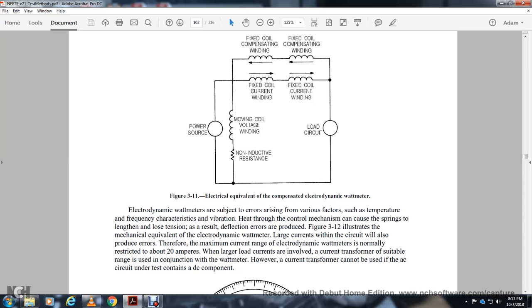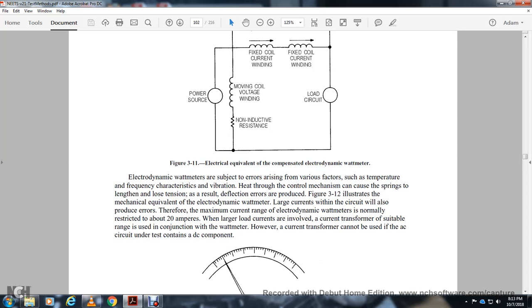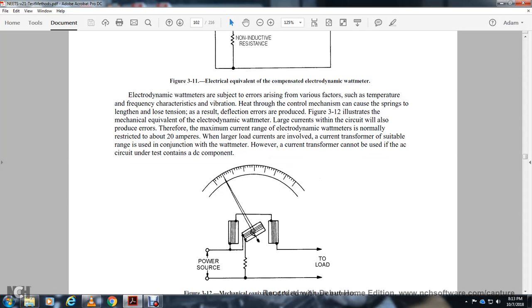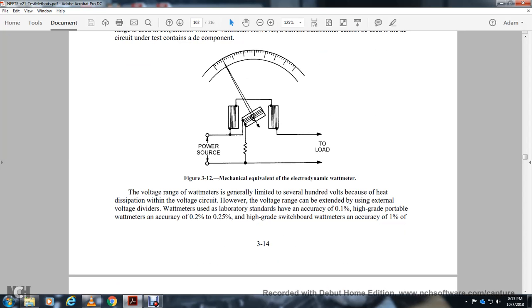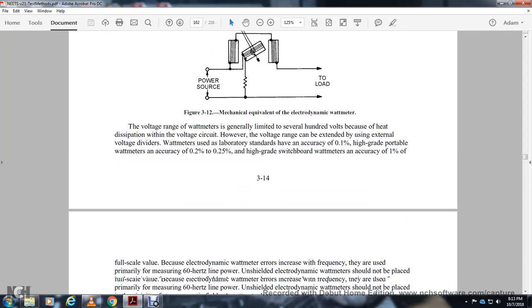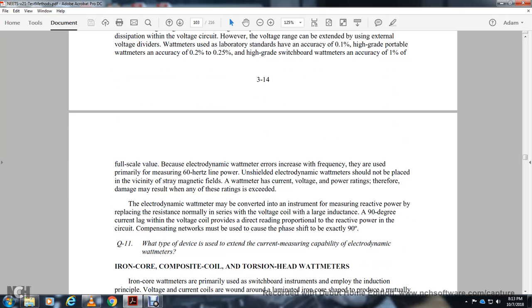The current transformer cannot be used if the AC current under test contains a DC component. The watt meter is generally limited to several hundred volts; external voltage dividers extend the range. Laboratory standard watt meters have accuracy of one-tenth of a percent. High-grade portable watt meters have accuracy of 0.2 to 0.25%. High-grade switchboard watt meters have accuracy of one percent of full-scale value.